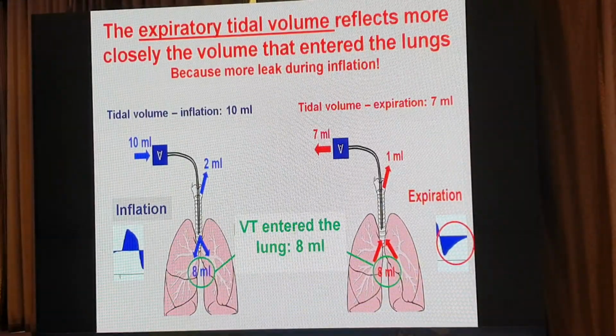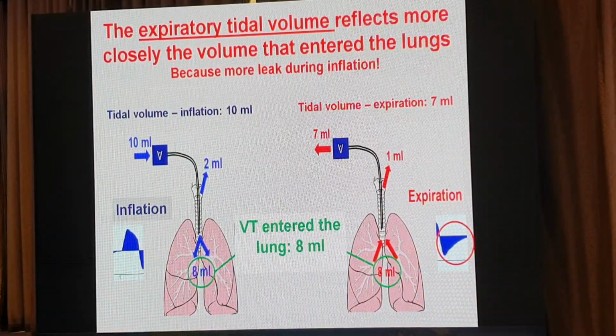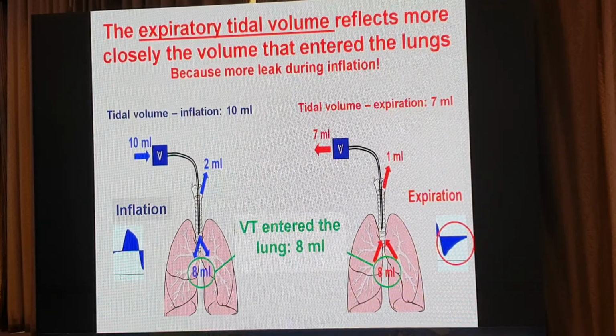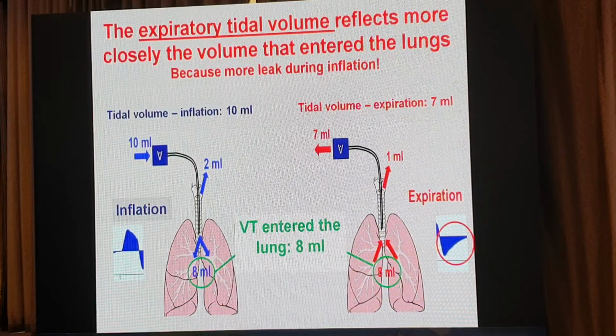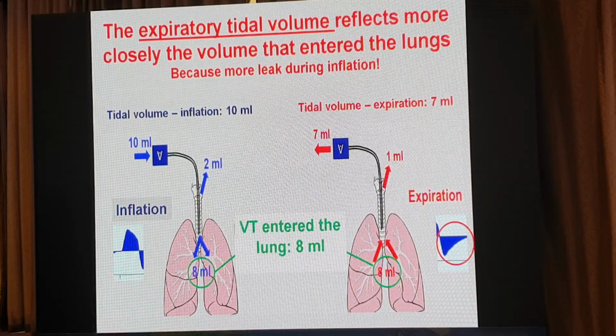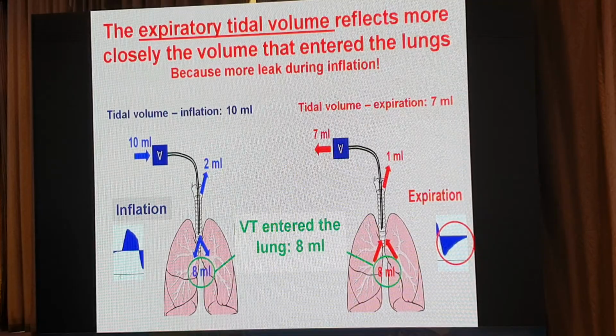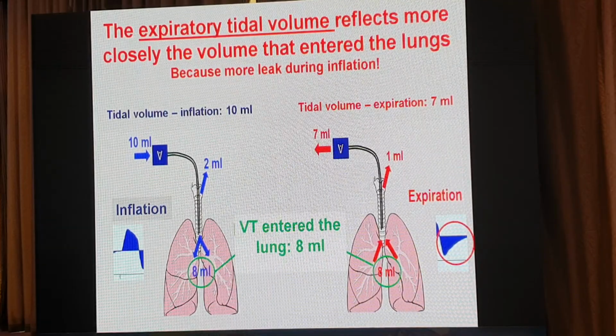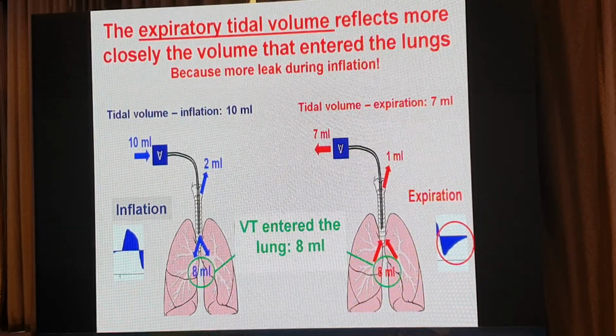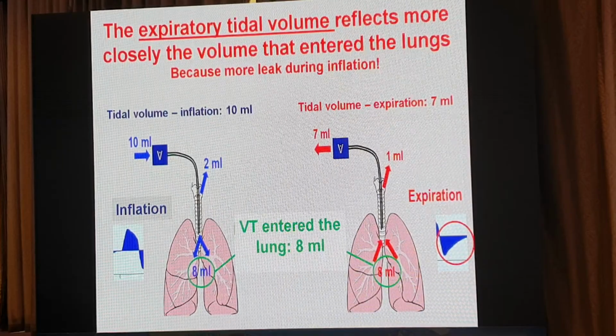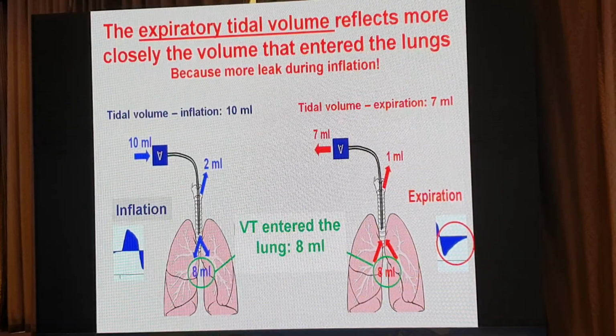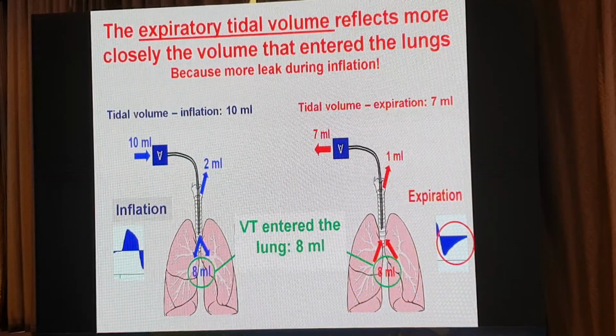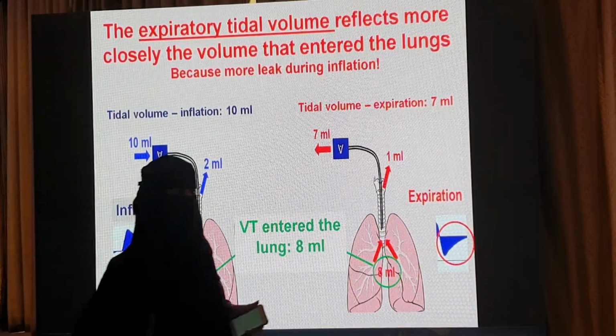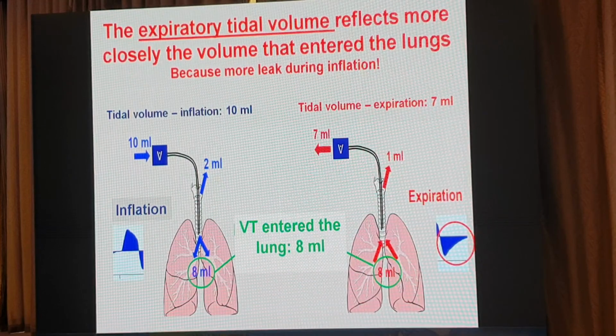When you're doing targeted tidal volume ventilation, it's usually the expiratory tidal volume that is used for calculating what you're aiming for. This is because the expiratory tidal volume reflects more closely the volume that enters the lungs. There's more leak during inflation, so if the volume going in is high, you will lose a certain amount of that volume. But if we measure what's going out, there's little leak on the way out. So what is coming back from the lung is what really reflects what has entered the lung.